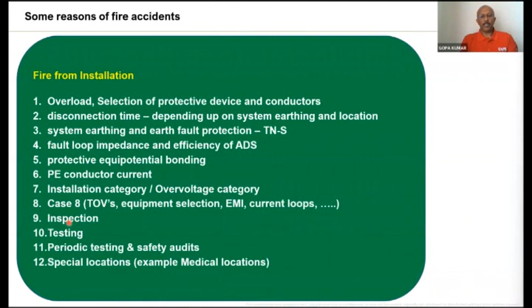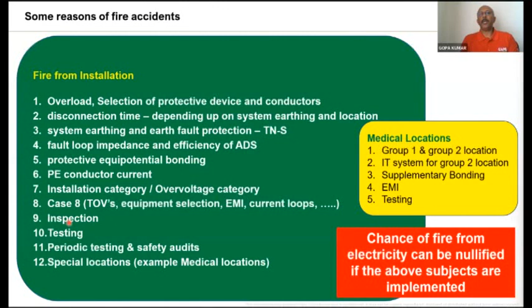If we are able to take care of all these 12 points, plus the additional points, such as, in a medical location, the risk assessment and all these things, we can get an electrical installation where the chance of fire from electricity can be almost nullified. The chance of fire is nullified in the sense that there is no chance of fire. In case of any problem, your MCB trips. And in case of a group 1 and group 2 medical location, IT system, the MCB need not trip. You have a medical insulation monitor. So without MCB tripping, you achieve safety.